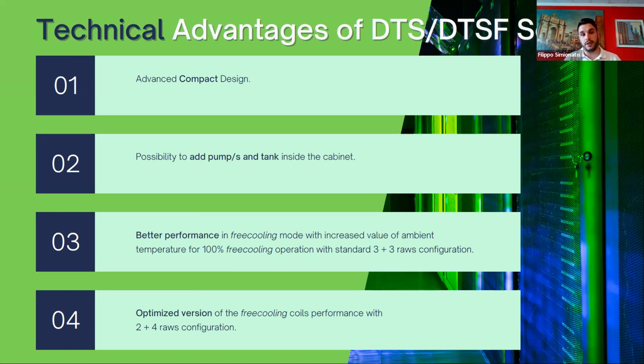having this opportunity, so having also the opportunity to customize the unit, we have the possibility, on this series, to add pump or pumps and tank inside the cabinet, because we see that in particular for data center application, a hydro module connected or related to the chiller, or inside the cabinet of the chiller, is now asked. But it also gives the opportunity not only to customize the unit using, for example, an inverter compressor, to follow the load that the customer needs, but also to add an inverter on the single pump or on the double pumps, giving the customer the opportunity to better follow the flow rate of the system.